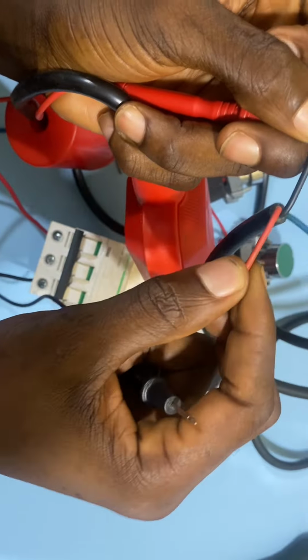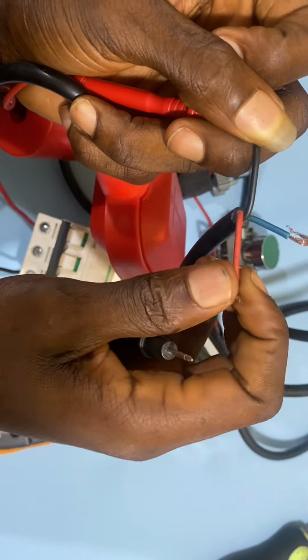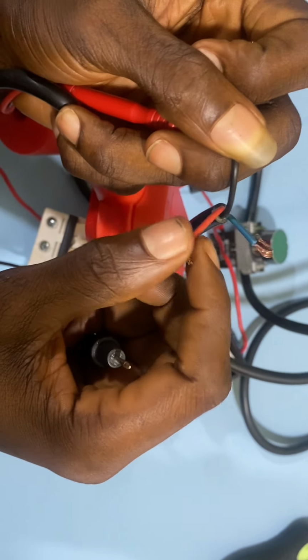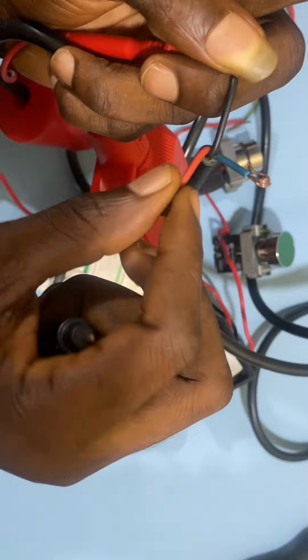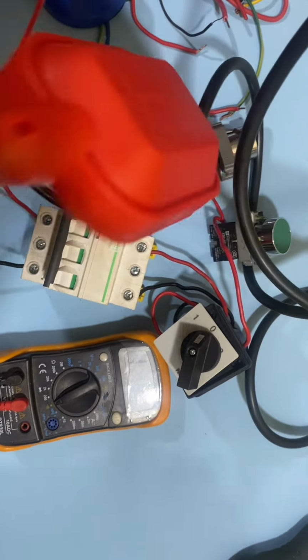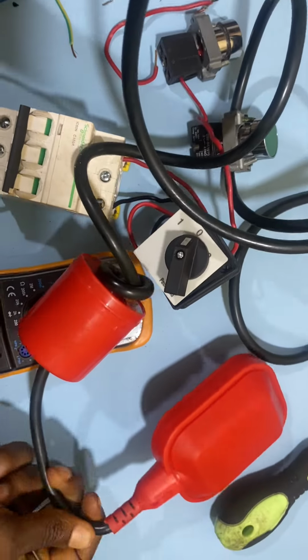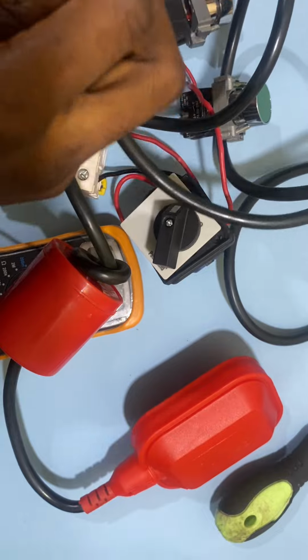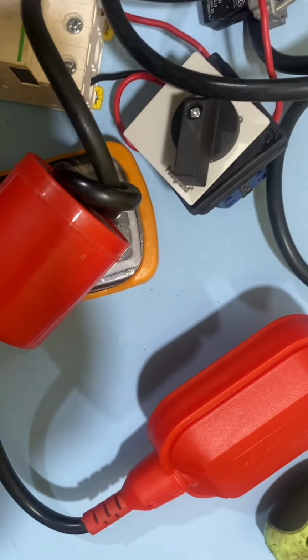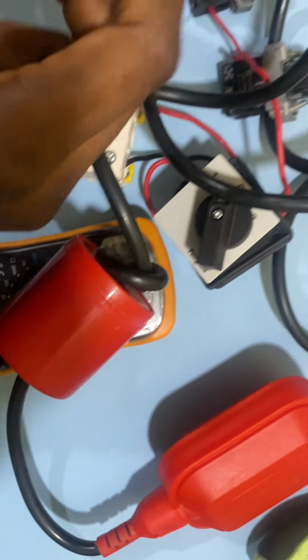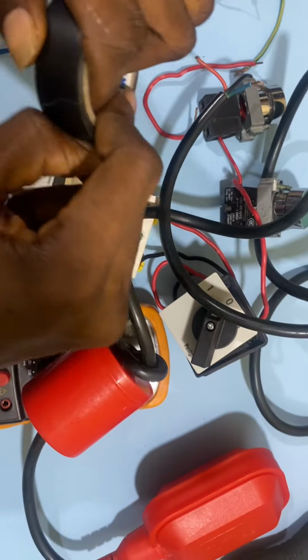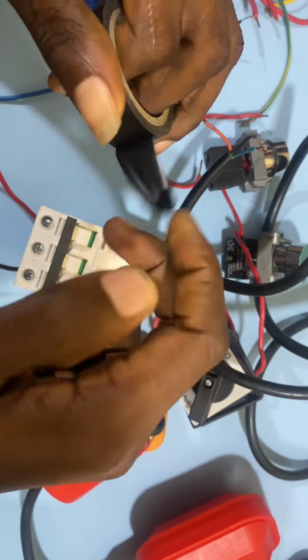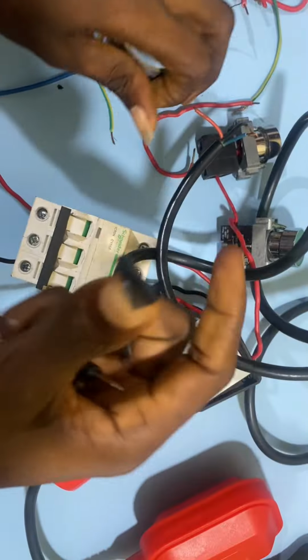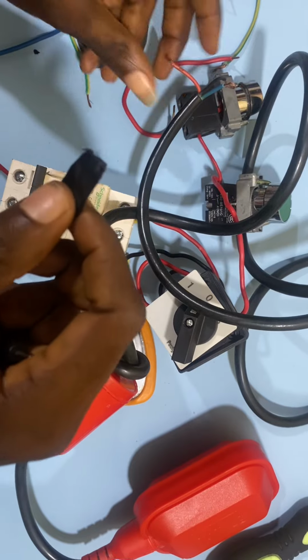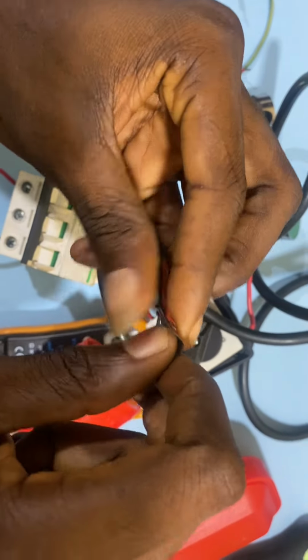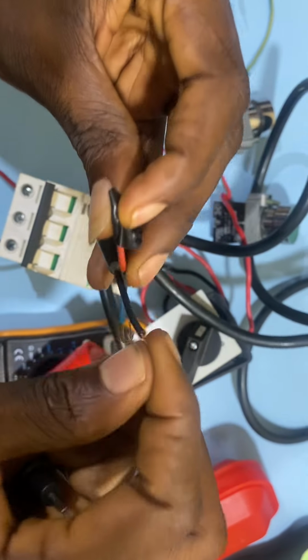Since we are not using the normally closed terminal of the float switch, we are going to insulate the normally closed terminal of the float switch. So let me do that quickly. So just follow me, let's do it together. So this is my insulation tape. So I'm going to use the insulation tape to insulate that point that we are not using. So this is normally open, so I'm going to insulate it at this point.